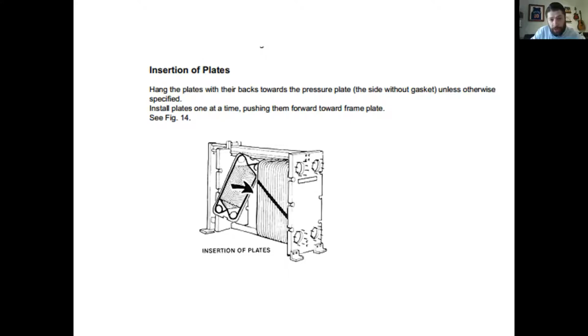So in this picture, you see how they sort of swing out. They're showing you the insertion. Basically, there's a cutout at the top of that plate, sort of like a hook. It hooks onto the bottom of that bar, and it swings in. So in this drawing, you can see on that right side, if we're facing the front plate, you're going to need only a few inches on that side. And then to the left, you're going to need 1.5. That's what you're going to need to get that plate out. Okay? So that's why we say 1.5 on one side, and you don't want to be jammed right up against the wall on the other side either. You're going to need a few inches there.